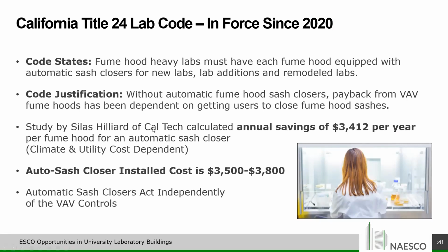Regarding the auto sash closer, this is in California Title 24 in the Energy Building Code. The new code for laboratory spaces, whether new lab spaces or retrofits of existing labs, calls for an auto sash closer to be installed on every hood. The reason is a study done by Caltech, estimating that an auto sash closer will provide an annual savings of about $3,400 a year. You can see that because of how expensive laboratories are to run, and how expensive fume hoods are to maintain and feed with the amount of air. So auto sash closers are very important, not only for safety, but also to guarantee the energy savings.